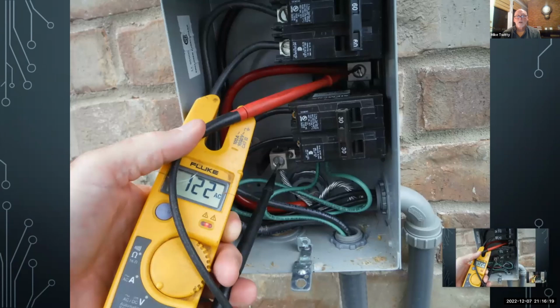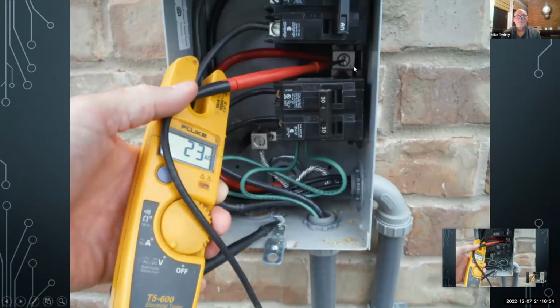I'm showing a measurement. This is another one, and I'm reading from this hot lug to the ground lug, and I'm getting 122 volts as I should. I'm reading to the equipment ground that's coming in here, same panel. Now I go from the same hot lug to the metal can. This is just a phantom voltage. There's no voltage here. I could see it visually because this is floating, lifted off of the can. This is showing through a meter that this cabinet is not bonded. That should have the same potential as when I put the other probe here. That's showing that there's a voltage difference, and that's dangerous.